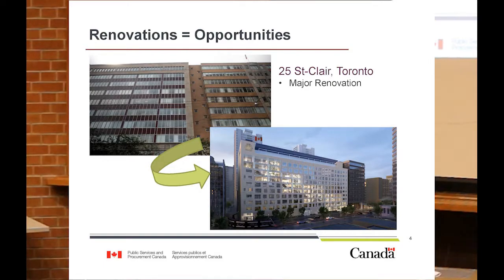You'll see the old building at the top, and a rendering of the new building. The current building has a water source cooling tower, but the new building is looking at going with a geo-exchange loop, which will significantly reduce risks associated with Legionella since we'll no longer have a cooling tower at that site. I believe they're also looking at a dry cooler or air-cooled chiller as backup, which also wouldn't have any water source associated with it.